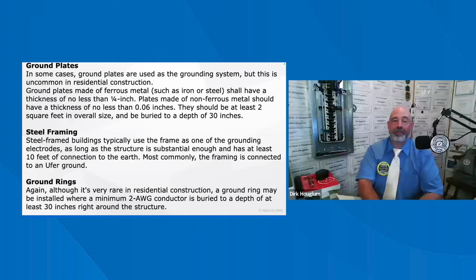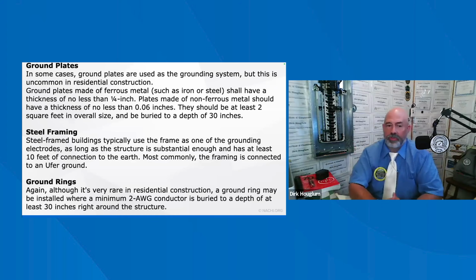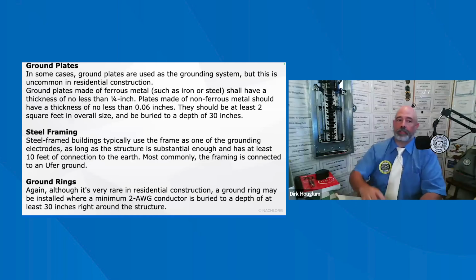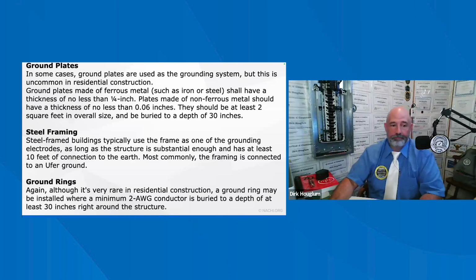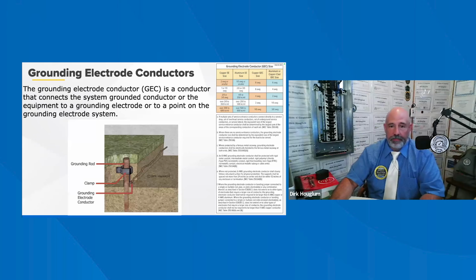So, 10 feet of connections to the earth. And then the ground rings, a lot of times these are more common like in pool structures and stuff, although it is very, very rare to see these in residential construction. A minimum of 2 AWG conductor is buried beneath the earth and at least 30 inches from the structure. So that's kind of it on that.